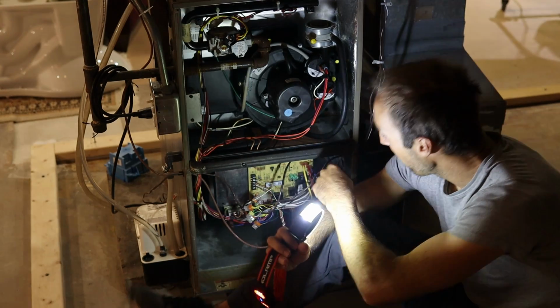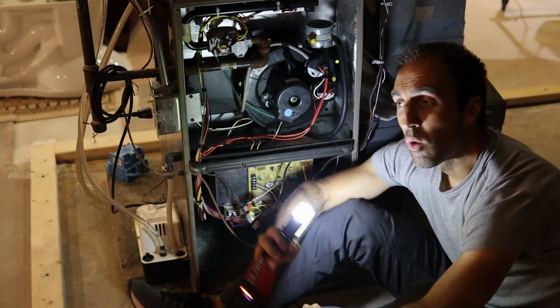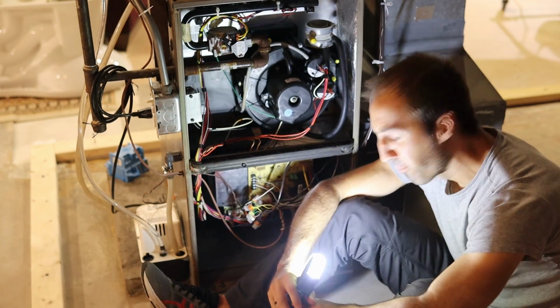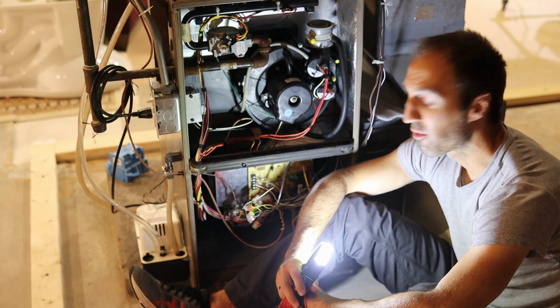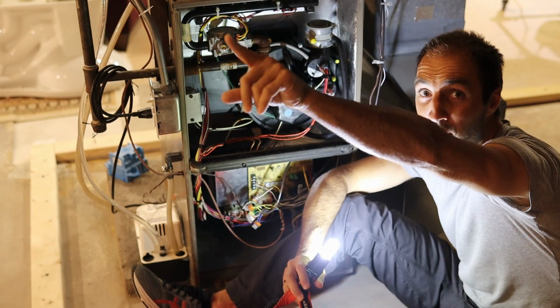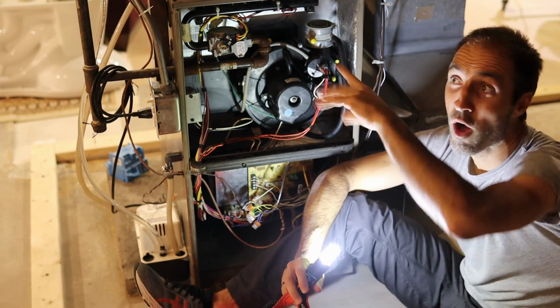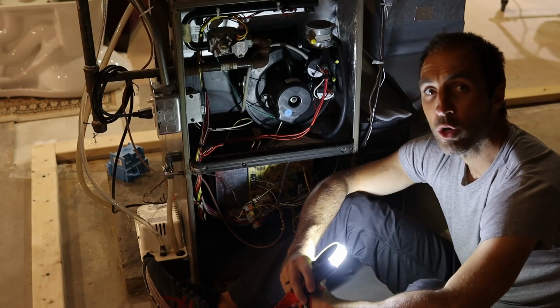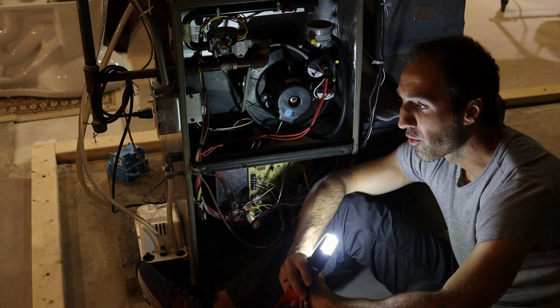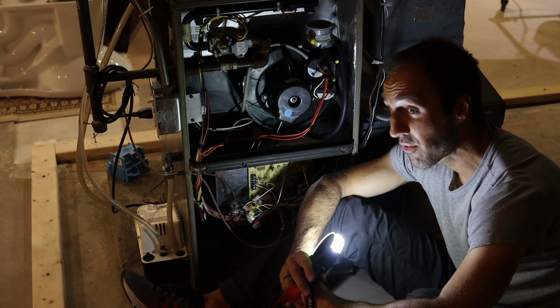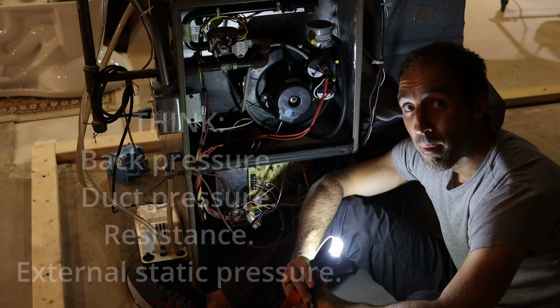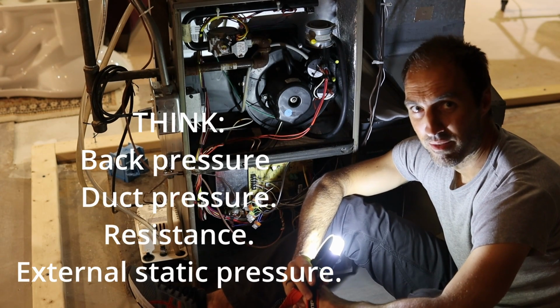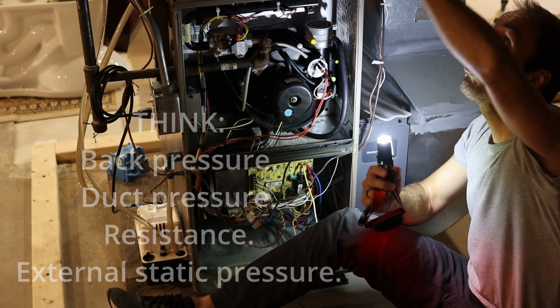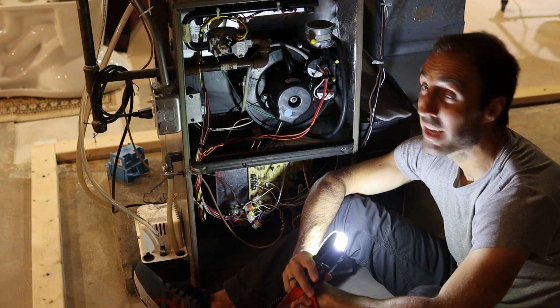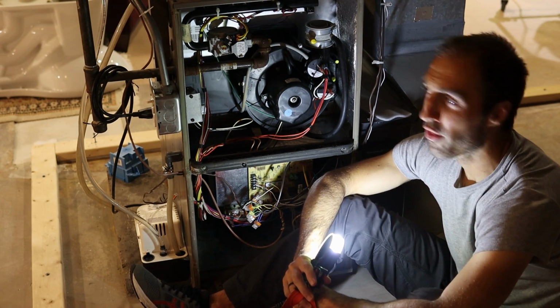Right now, let's just suppose that my blower motor will push 1,000 CFM on this blue speed tab, okay? And let's say my house needs 1,000 CFM. So it's perfectly matched up because I need 100 CFM for that room and 500 for that room and 300 for that room and so on. All the CFM equals 1,000, and on this speed, my blower motor will push 1,000 CFM. Well, folks, my blower motor will push 1,000 CFM of air at a certain pressure resistance. In other words, when air goes through my duct system, it has to push against the friction in the ducts and all the corners and the turns and all that stuff.